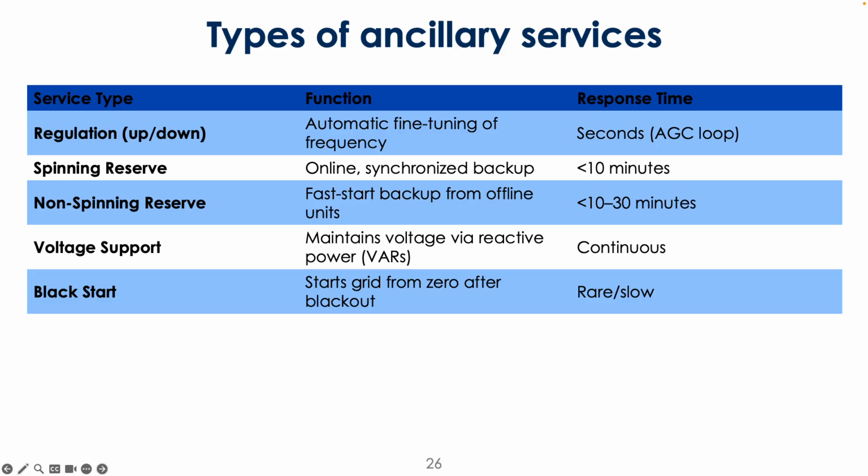And so if you had a generator that was just off, which we'll call a non-spinning reserve, then not only do you need to start spinning up to produce the electricity, you also need to get into sync with the phase of electricity in your grid. And so a spinning reserve is something that's already spinning and in sync with the electricity phase, and so you can connect it a lot faster, essentially. Yeah. So that's the difference between your spinning and non-spinning reserve.